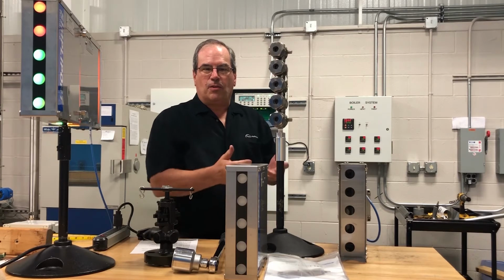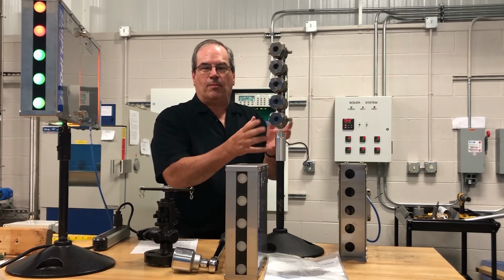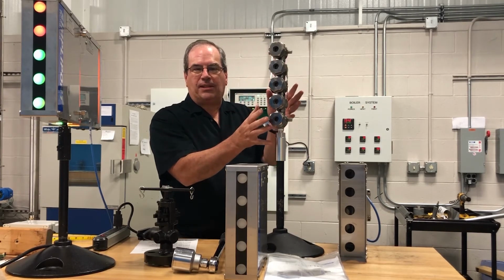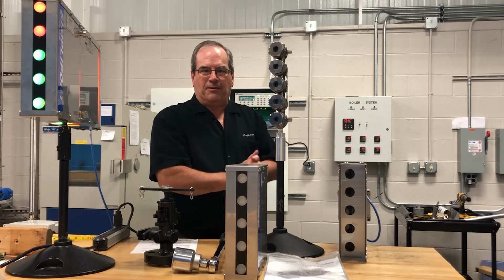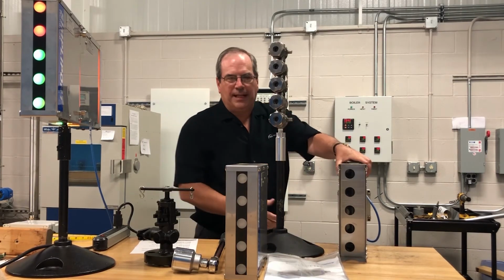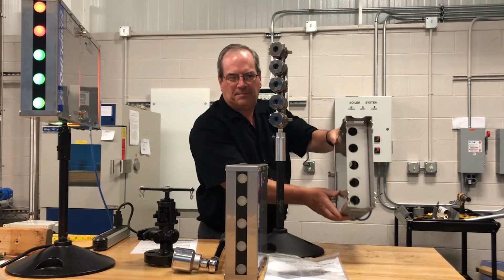gauge. Close the drain valve, open the steam and water valves slowly, bringing the equipment back into a normal operating level position. Verify that there are no leaks. If you see any leaks, isolate the gauge and open the drain valve and take care of the problem, and then repeat. Install the illuminator on the back of the gauge first, and it simply attaches onto the mating connections.